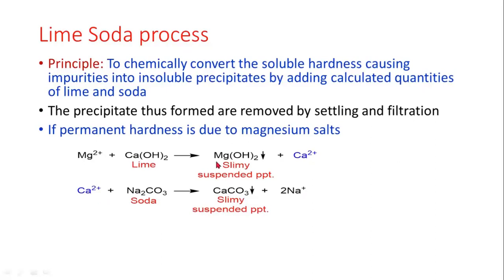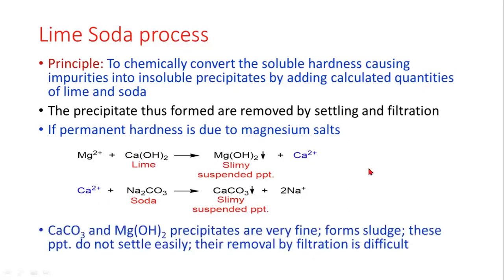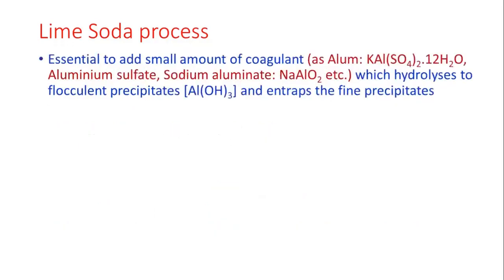In the lime soda process, calcium carbonate and magnesium hydroxide precipitates are formed as suspended material. These precipitates — calcium carbonate and magnesium hydroxide — do not settle easily, so we remove them by the filtration method. Some coagulants such as alum or sodium aluminate are used, which convert the fine particles into hydroxide and help them settle as distinct precipitates.